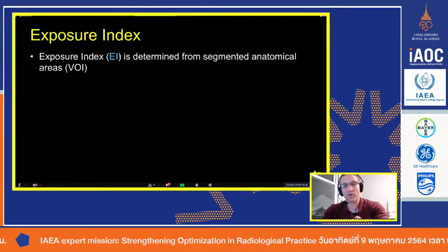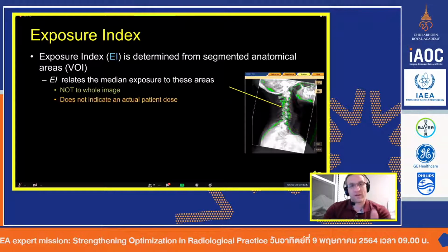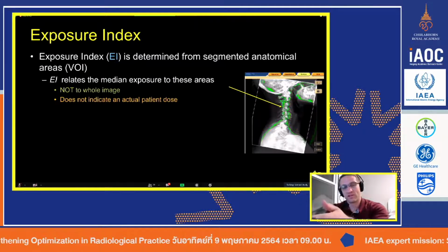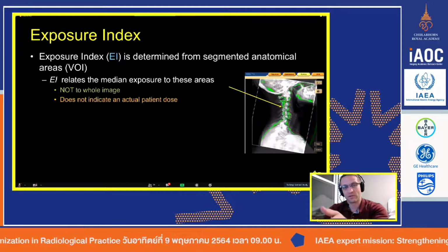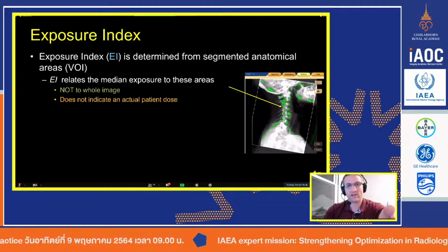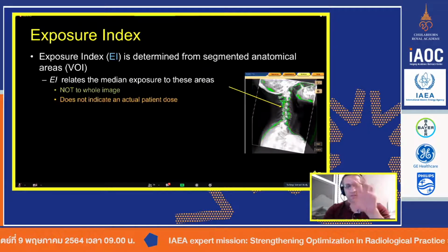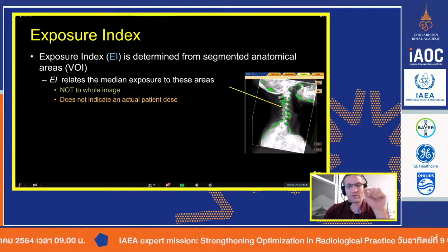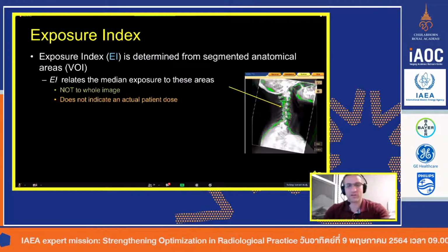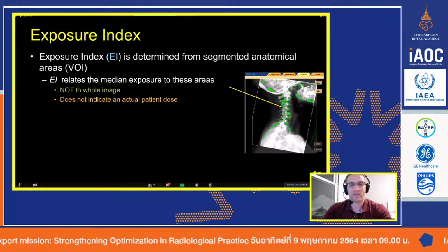So now we're going to use the EI to verify that in real time, every time a patient is exposed. They're examined, they get their exam, and then the images show up in PACS. And Tanya and all her radiologist friends have talked to the PACS people, and now they see EI at the bottom corner somewhere on their screen, and they're going to look at that value.